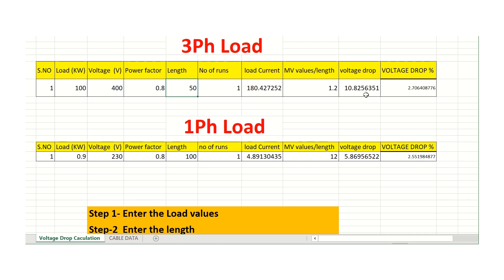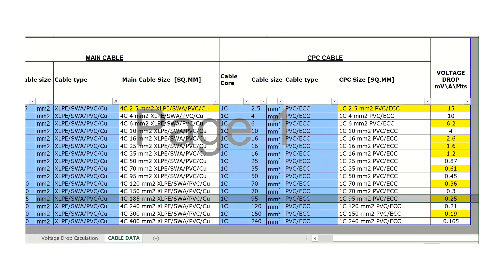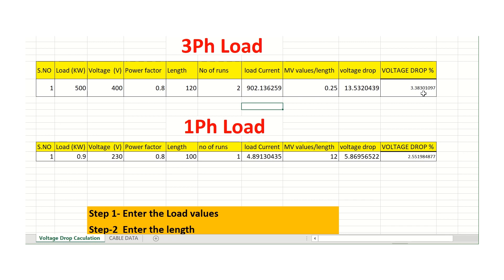For the last example, consider a 500kW load over 120 meters. Going to the cable data sheet, I try a 4-core 185mm² cable (MV = 0.25). Entering 0.25 gives a voltage drop of 27.06V and 6.76%, which exceeds 4%. Running a second parallel cable of 4-core 185mm² reduces this to 13.53V and 3.38%, which is less than 16V and under 4%. So for 500kW over 120m, you need to run two 4-core 185mm² cables.